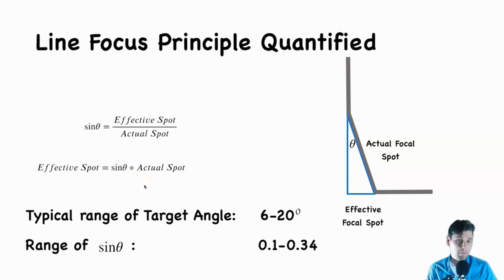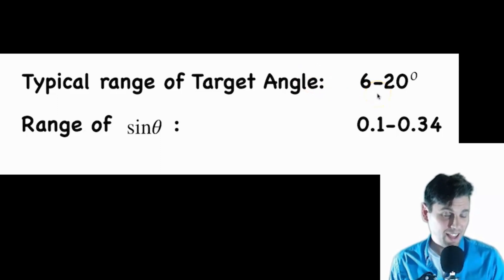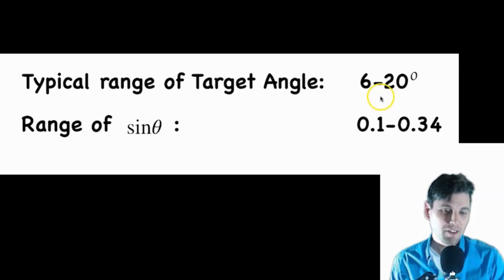What does that mean in practice? The actual angles are typically small, such that we can take good advantage of this effect. In practice, tube angles are typically between 6 and 20 degrees for an x-ray tube. So if you do it in radians, theta is very similar to sine of theta, but you can also just type in sine of theta in your calculator if you're doing it in degrees. The sine of theta is between 0.1 and 0.34.